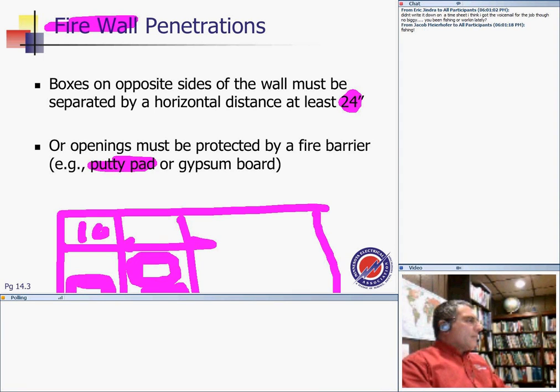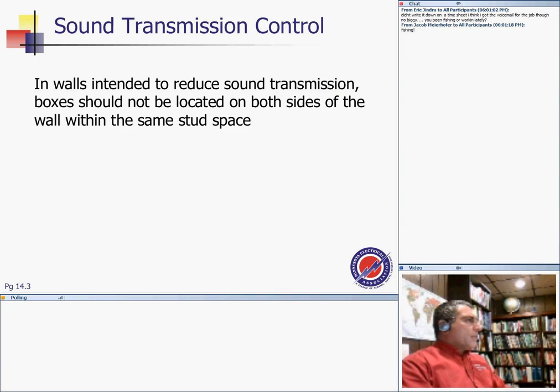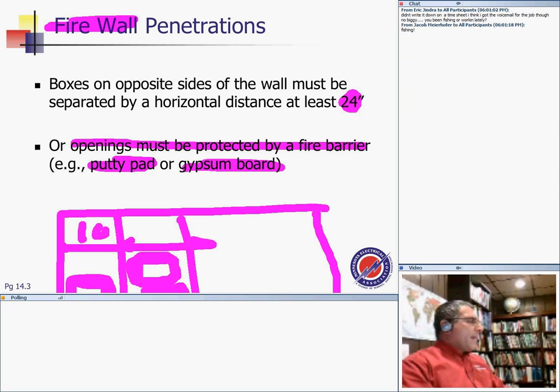Putty pads, gypsum boards to maintain the opening must be protected by a fire barrier. So pay attention to fire-rated walls and penetrating the fire-rated wall. Either you're going to use some type of putty pad to seal it to maintain the integrity of the fire rating. Fire-rated walls, Joe, my friend, are meant so that if there's a fire in one area, it will not spread to the other area. So the walls go all the way up to the structural ceiling in the building, unlike other walls where they can go up to and slightly above the suspended ceiling, and they stop.